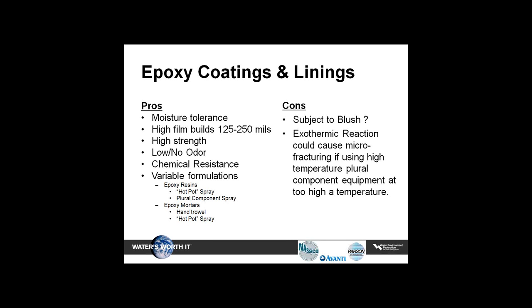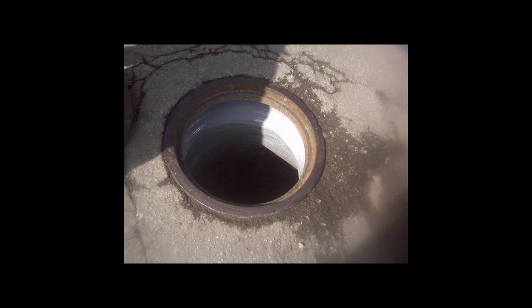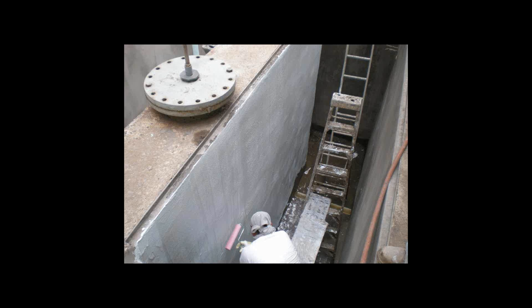The cons of epoxy linings are they are subject to blush — certain constituents create a waxy film on the surface, though this doesn't really matter in a manhole. The exothermic reaction is a concern: if materials are applied too hot, they will cause cracking or brittleness of the film. Shown here is a completed manhole with epoxy coating, an epoxy in a wet well, and a super manhole that had complete aggregate showing, with 250 mils or a quarter inch of epoxy in the structure that extended its life.